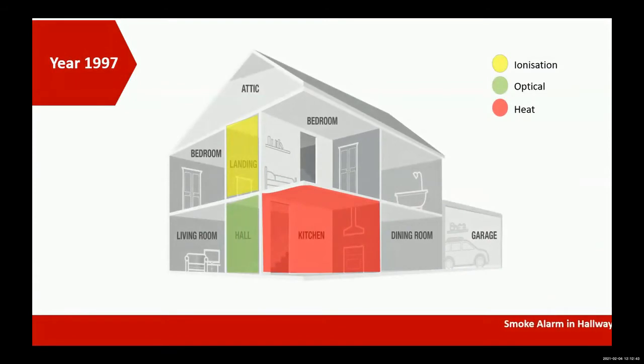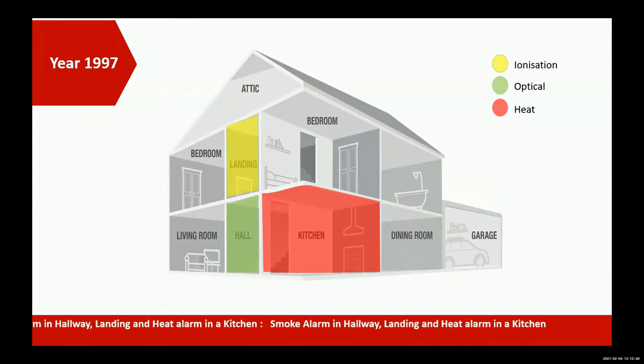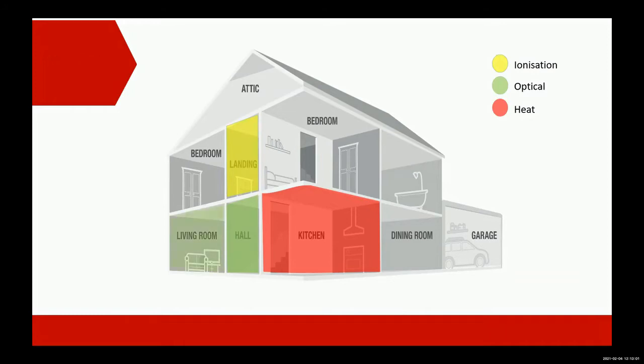So if we look at year 1997, what was required at that stage was a smoke alarm in the hallway, a smoke alarm in the landing, and a heat alarm in the kitchen, and that was basically it. And that was, again, as I said earlier, covered by BS 5839 Part 6, same reference. In 2006, we looked at Part B again, and that was upgraded, and they added the principal living room into the equation at that stage. We moved from three devices up to 4 devices in 2006.